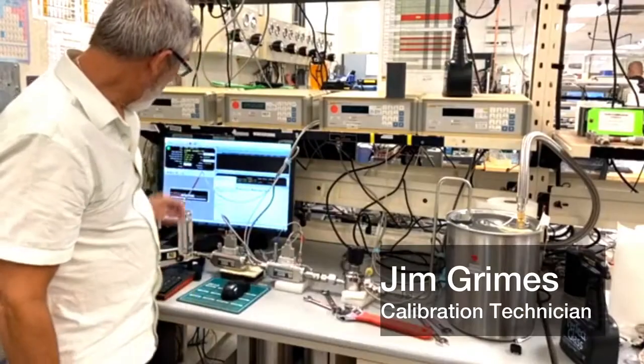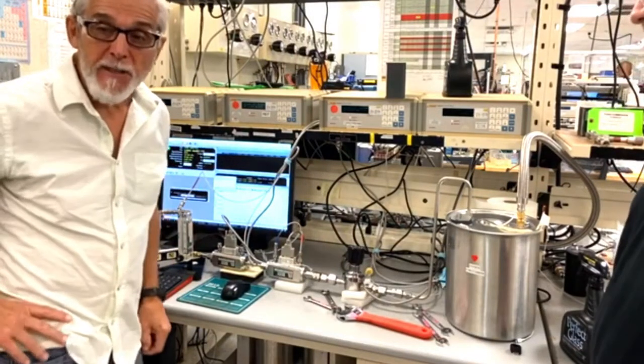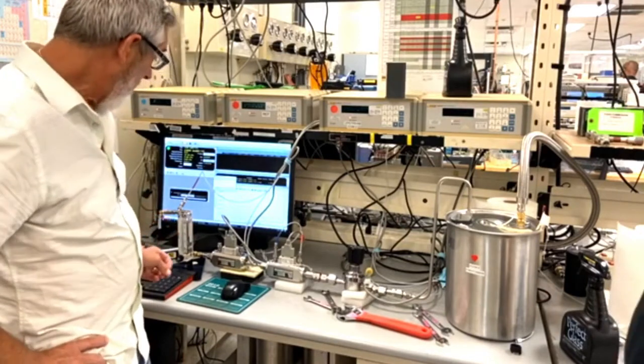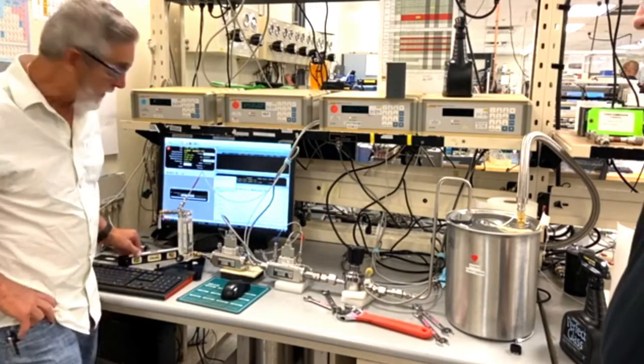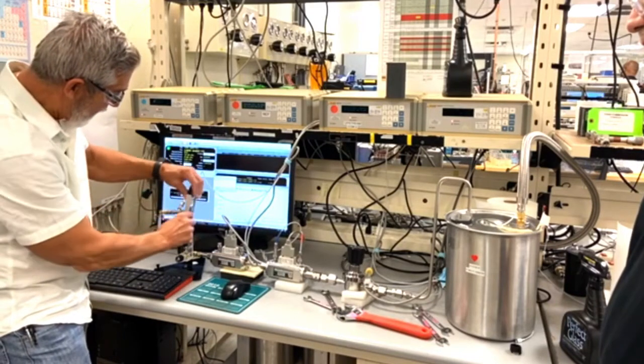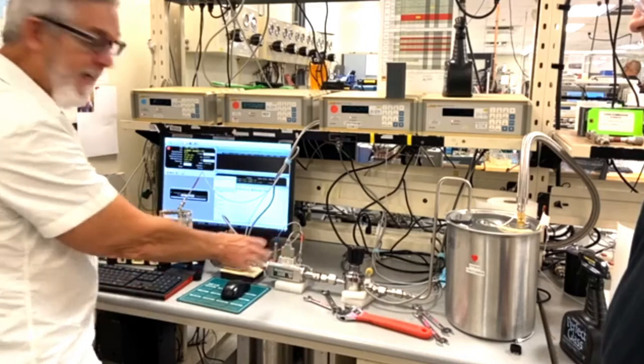Hello. This is a rotameter that exits to the atmosphere. There are plenty of rotameters that have different pressure and flow conditions. The way we set one of these up is, first of all, we level it in all three directions. And then we make sure it's properly connected with no leaks.